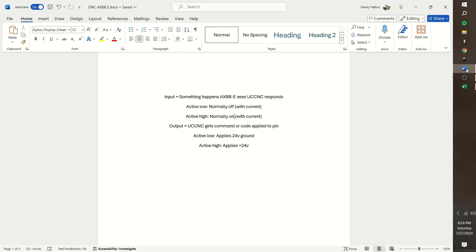For an output, it is much simpler. Active low condition means it applies the 24 volt negative or ground. Active high means it applies the plus 24 volt positive. An output would be used for relays.